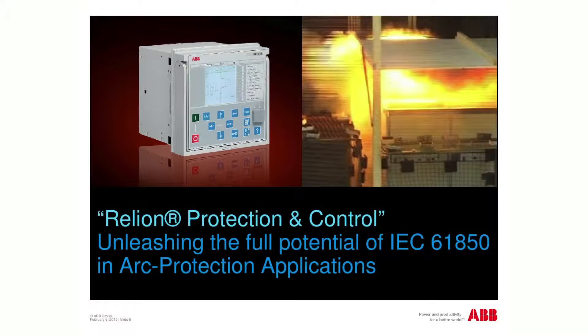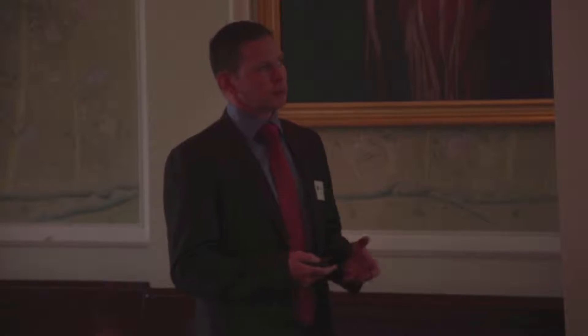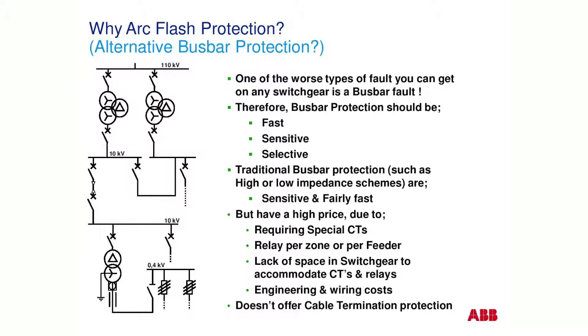There are numerous features, numerous advantages and benefits of the Relion family. One of those features is this integrated arc flash protection. Bus bars often do get faults from time to time and the worst kind of fault is an arc flash. Arc protection's main purpose is to trip very, very fast before that arc can get out of control and cause the maximum damage.